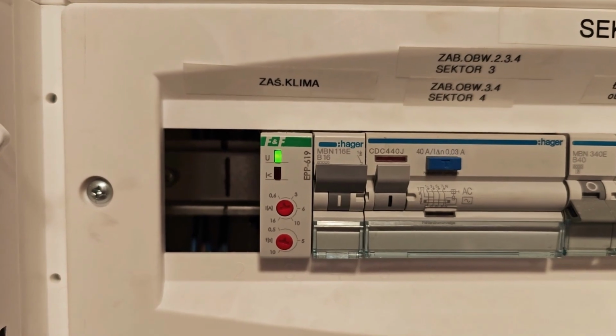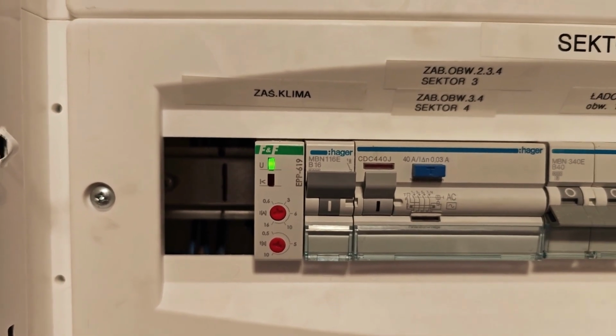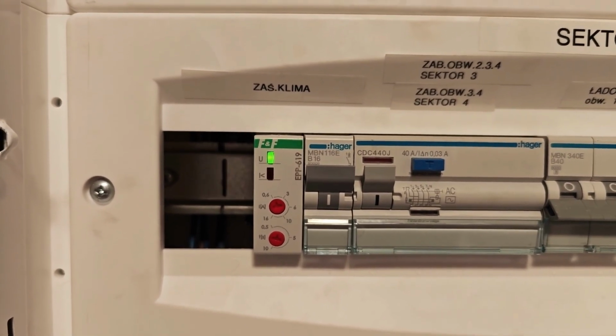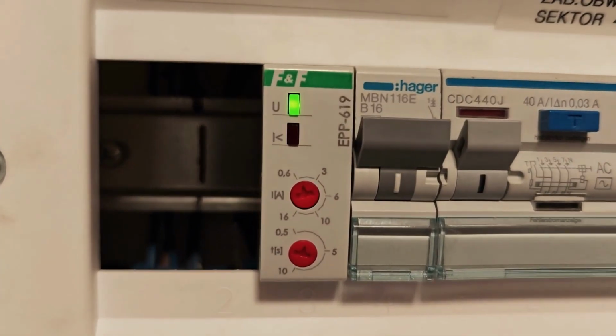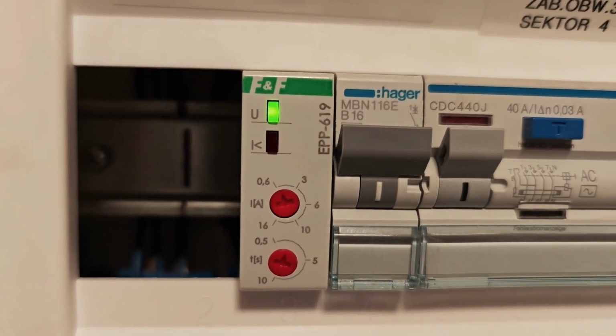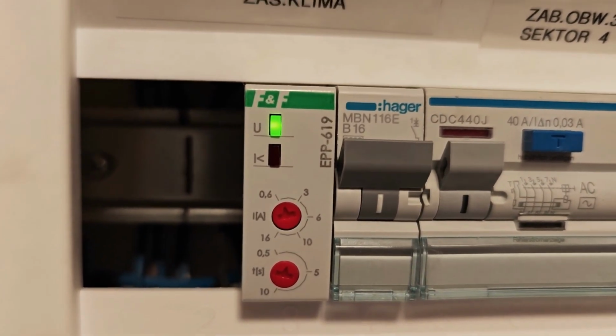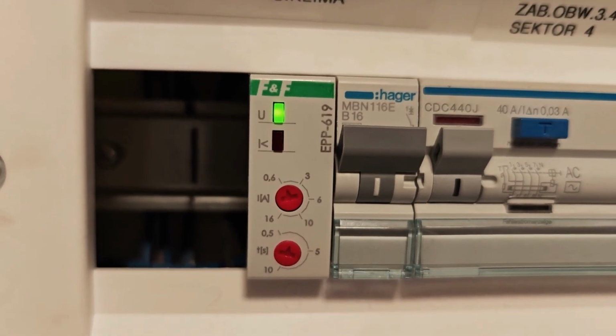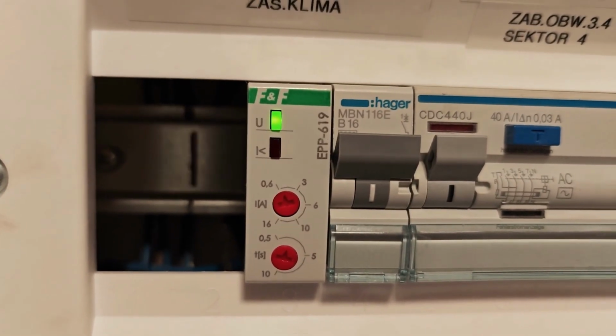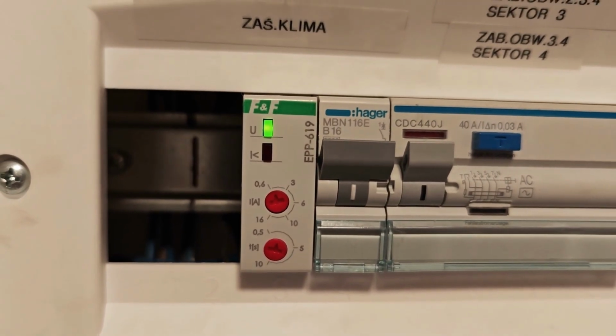The solution turned out to be a relay that was placed inside the electrical box. It monitors the current consumption of the air conditioning unit, and when it's active, it supplies power to both the fan and the actuator. This then causes the recirculation system to engage. Upon the unit's shutdown, the actuator reverts to its initial position and the fan ceases its operation.